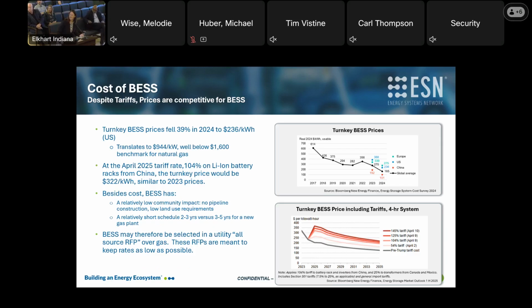You can see here the average US turnkey cost, meaning you've not just manufactured the cells but put them in packs, in racks, in the container, built the fire suppression system and temperature sensors, and deployed it to the field—it's only $236 per kilowatt hour. That's a cost per energy, typically quoted as dollars per megawatt hour or kilowatt hour. So if you ever need to do property assessments, it goes by energy typically. That's $236 per kilowatt hour, which is extremely low, and even the highest tariffs presented aren't impacting that greatly.